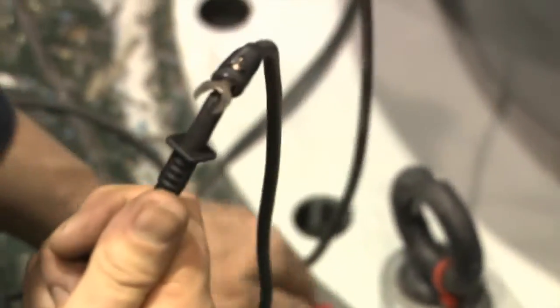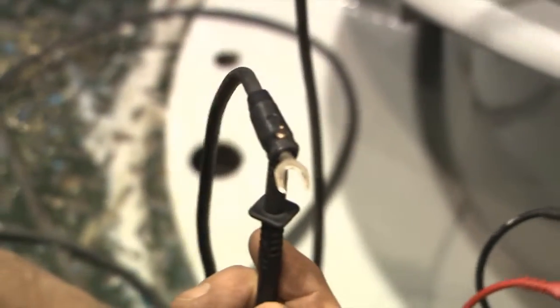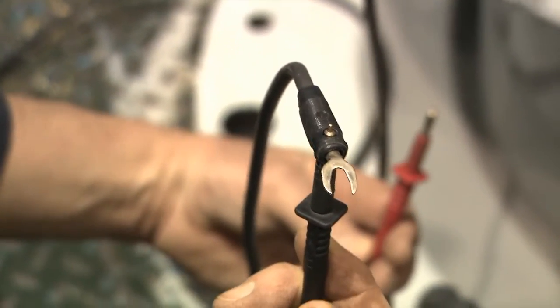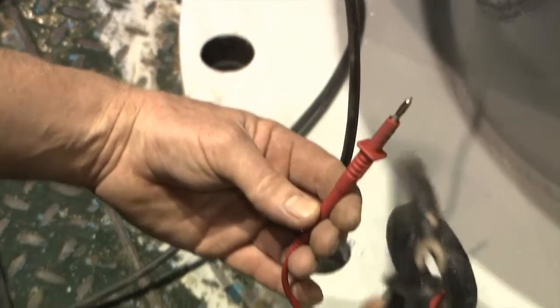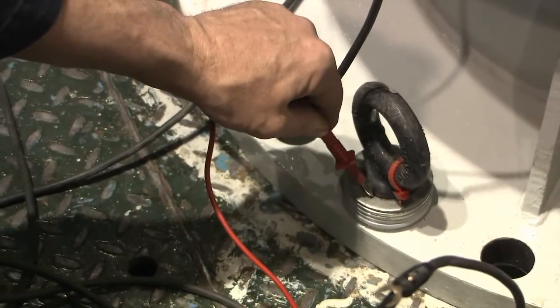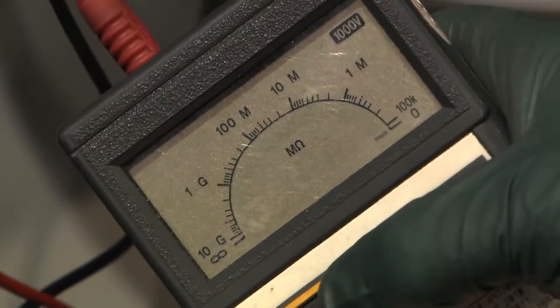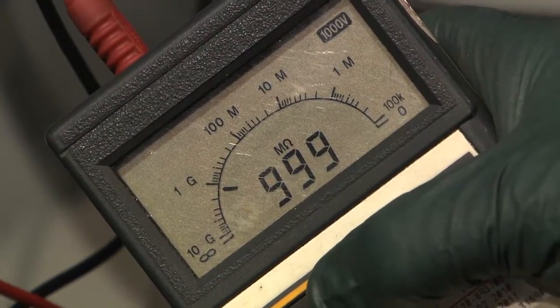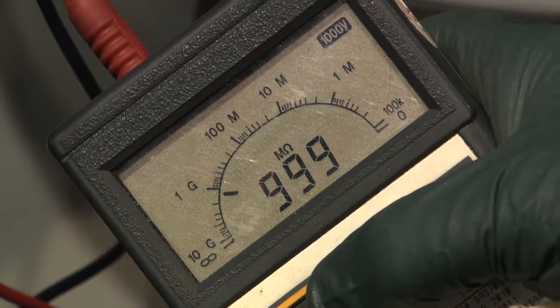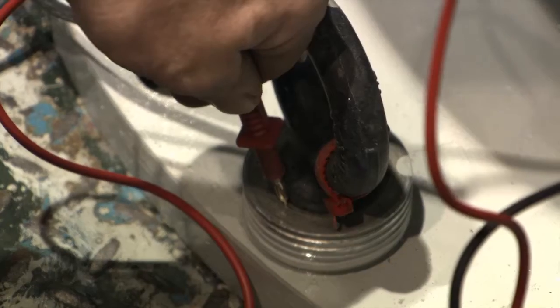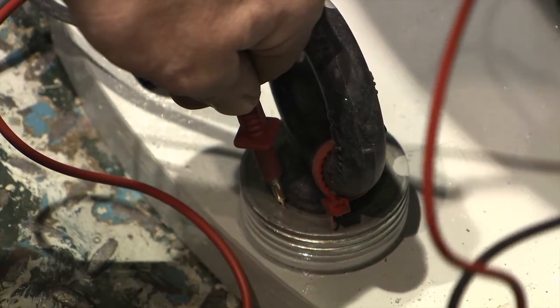Neato. It's just going to go to contact on the flange. There it goes. That's a good number, right? Yep, greater than 999. Yeah, see? It's not as good a connection through there. That's not grounded out properly.